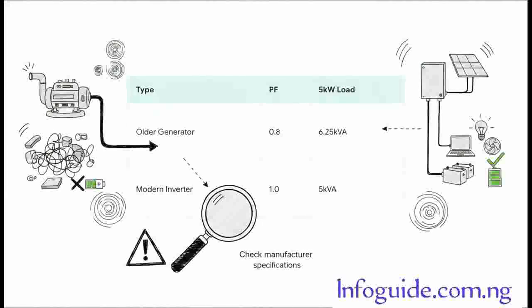You'd actually need a 6.25 kVA generator to handle it, because 5 divided by 0.8 is 6.25. But contrast that with modern hybrid solar inverters. A lot of these newer high-tech units operate with a perfect unity power factor of 1.0. In that specific scenario, multiplying by 1 means 5 kVA perfectly equals 5,000 watts.